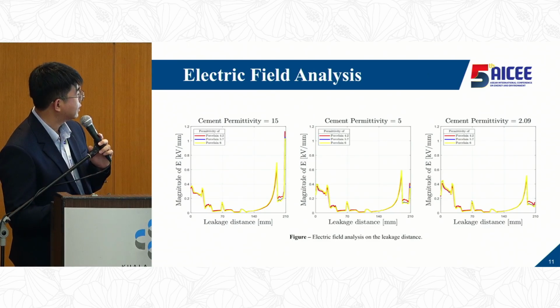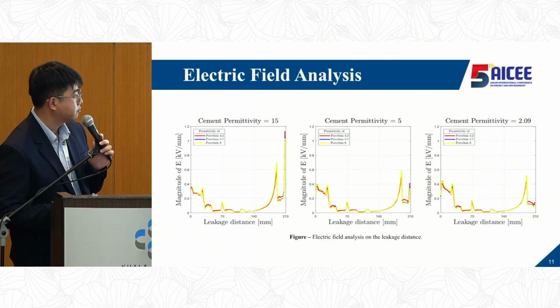From the electrical field analysis, we noticed that at the beginning, the electrical field for the porcelain with permittivity of 4.2 is the lowest, but near the cap it shows the highest density. Comparing cement permittivity values of 15, 5, and 2.09, we notice that the lower the cement permittivity, the lower the electrical field at the cap.